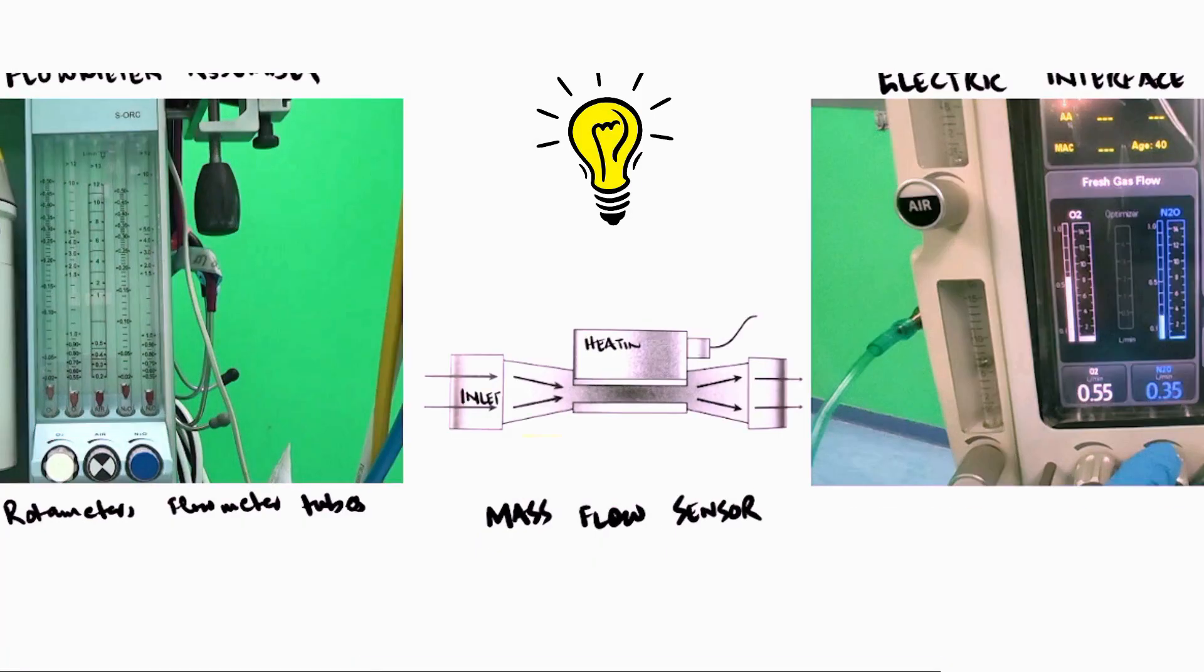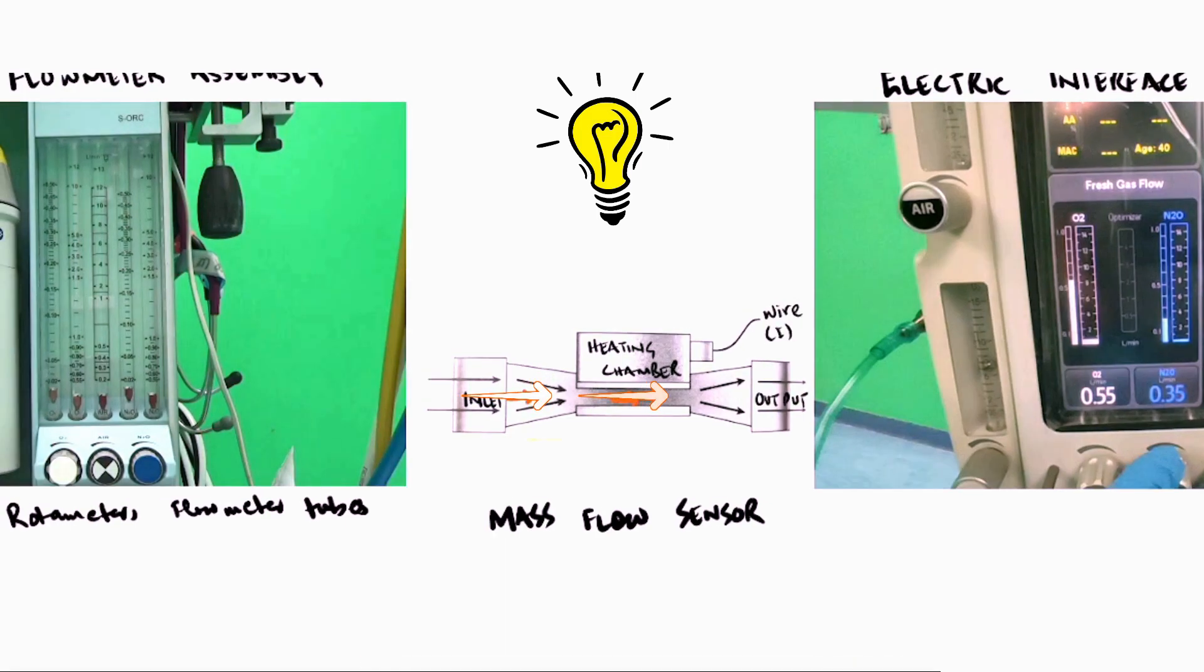In electronic type flow meters, the flow sensors are electronic too, such as vanes anemometer or mass flow sensor. Let's see how mass flow sensor works. Now it has an inlet, a heating chamber powered by electric wire and an outlet. When flow enters the heating chamber, the chamber keeps the temperature of the gas constant. Now if you increase the flow, the chamber would require higher electricity voltage to keep the gas temperature constant. This change in electricity requirement helps it sense the total flow passing through the chamber. However, since these sensors are power dependent, the machine has a mechanical backup as well in case of power failure.